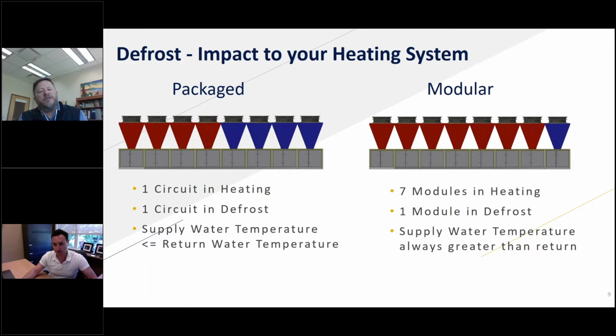So now when we start to look at whether it's a multiple, it's going to go back to what I talked about before, you have my packaged unit. If I look at a modular setup, or as I said before, if I had, in this case, 8 modules with 1 of them in defrost, 7 are in heating, or you could consider having 8 packaged units with 1 in defrost and 7 in heating, if the building automation system has the ability to tell the heat pump when it can or can't go in or out of defrost. What you end up with now is a system that can cycle through and provide defrost on each unit one at a time. But while it's doing that, it has a much different impact on your supply water temperature.